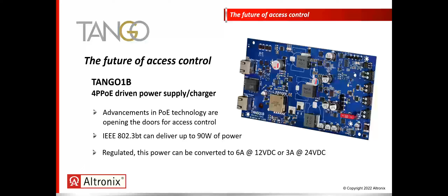The beauty of the new plug and play options for access control with the Tango 1B is that when we receive that PoE input of up to 90 watts, as you can see on the right-hand side, there are 2 sets of terminals that can deliver both 12 volts DC and 24 volts DC simultaneously. There's also a power and battery supervision terminal, so we can monitor that the power input and the batteries are connected to the unit. The battery charging circuit is set up to do LiFePO4, lithium iron phosphate battery charging.